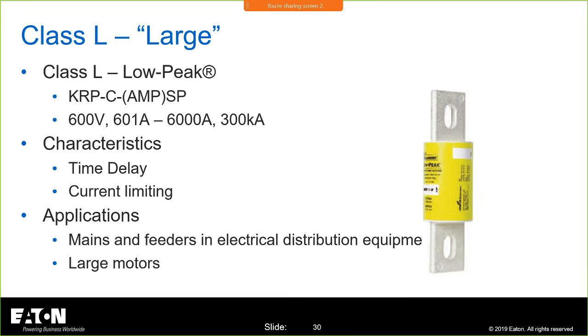Here we go. Class L. Class L fuses, large. These are your 601 to 6,000 amp fuses. Time delay, current limiting. You'll see these at the main service entrance equipment, large equipment, and large motors will have these. Again, when you're talking up to 6,000 amps, these are big boys. You're going to have a big load. Either it's going to be the entire facility or it's going to be a big motor.